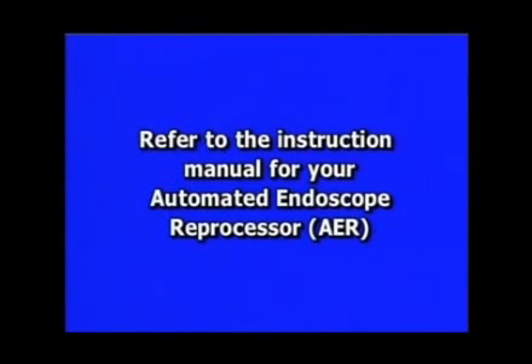If you are using an automated endoscope reprocessor, or AER, to high-level disinfect the bronchoscope, please refer to the AER's instruction manual. If you will be using an AER, you may want to skip directly to the next chapter. However, if you are performing manual disinfection, here are the steps for manual high-level disinfection.